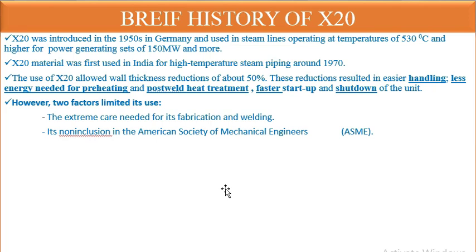However, two factors limited the use of X20. First, extreme care was needed for its fabrication and welding — parameters like PWHT, preheat, amperage, and voltage all required very careful handling. Second, X20 had non-inclusion in the American Society of Mechanical Engineers (ASME) codes, such as Section 9, which was a significant limitation.